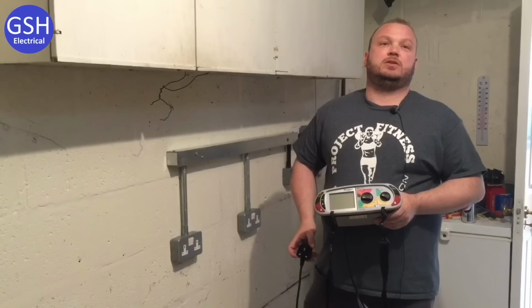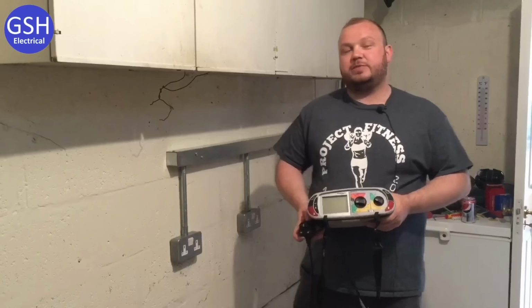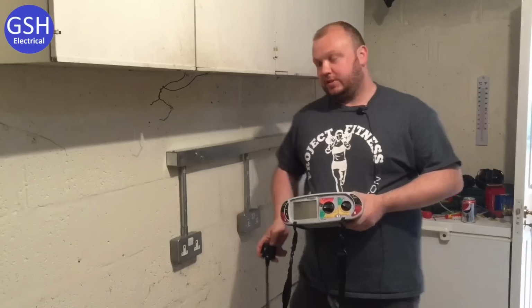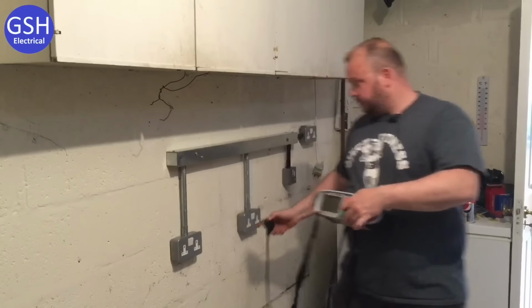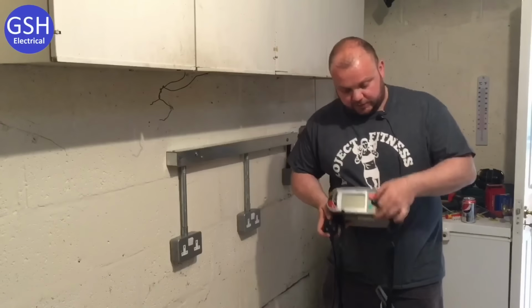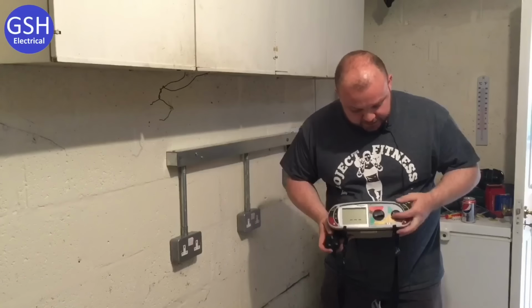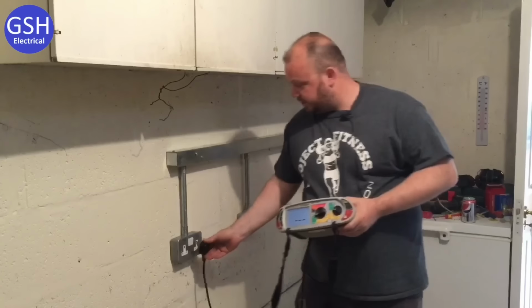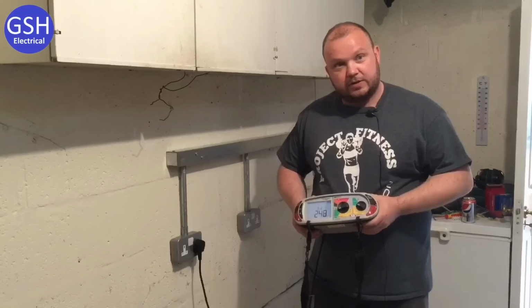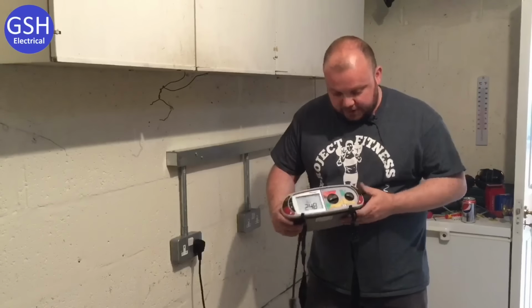That's correct. Okay. So what test are you now going to carry out for me, Mark? I'm going to do the earth fault loop impedance. Okay, test. Can you set your instrument up for me? I know we've tested the first socket, we've done these, but show us what you're setting your instrument to. I'm going to set it to LPE, and it's on Z. Okay, brilliant. And it says there, on 3 lead low, is that true? This is on 3 lead low.